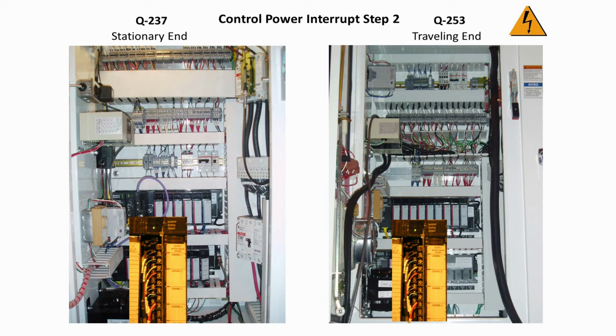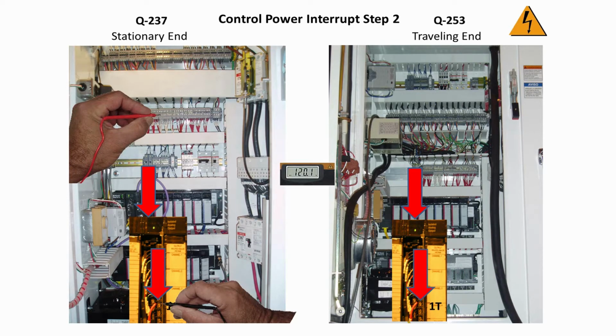Check number 6. If you do not have 120 volts on one of the output wire numbers at CR1 or CR2, then check the output wire number on the relay output module itself. If you do not have 120 volts, then on the relay output module, check the wire labeled 1S on the stationary end and the wire labeled 1T on the traveling end. If you have 120 volts on that wire number on the relay output module and not on the Q output wire number for either CR1 or CR2, then replace the bad module.